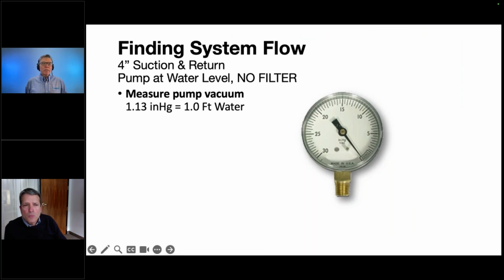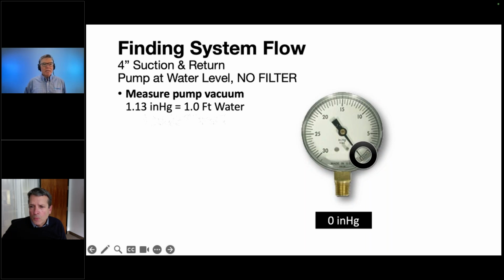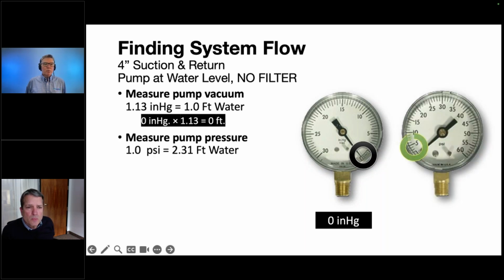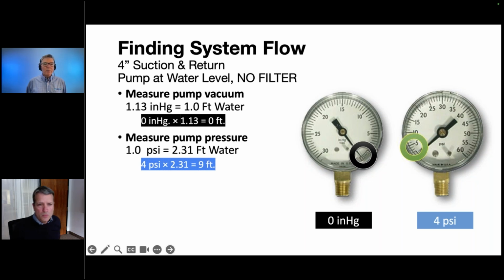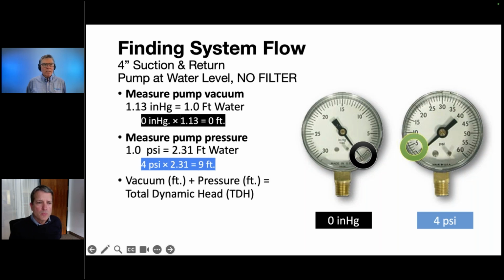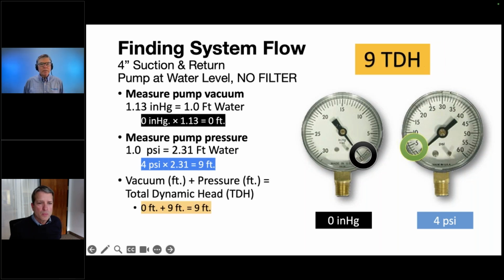The final step is we look at the other extreme, when we have 4-inch suction and 4-inch return. Again, we have a lab where we can do whatever we want with pipe size. The important thing to understand is this pump is absolutely at water level, not even 18 inches above, and there's no filter. So the inches of mercury, you can't even read it. The gauge sits at 0, basically. We actually use differential gauges. The back pressure was something like 4, again in the noise of the gauge, but it's close enough. We see this is 9 TDH.